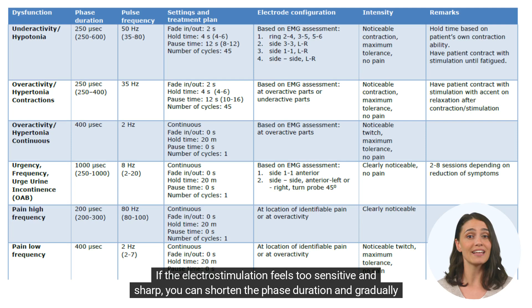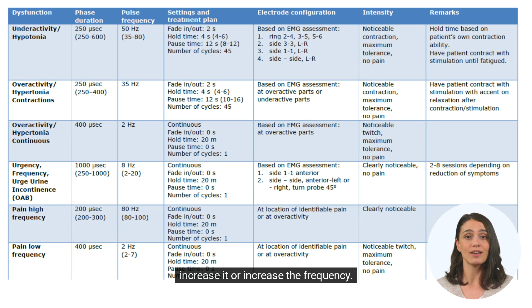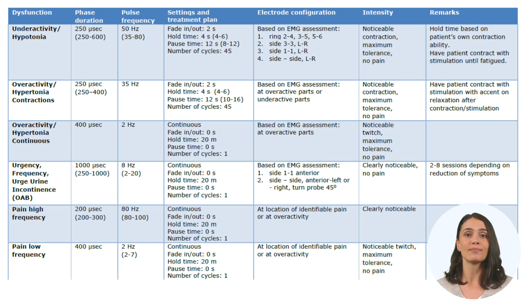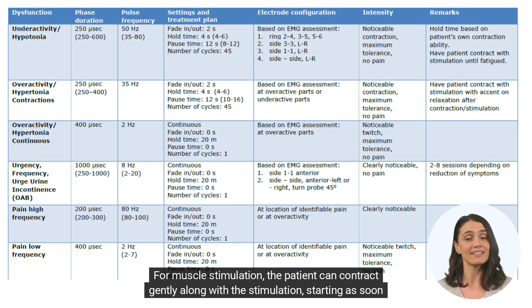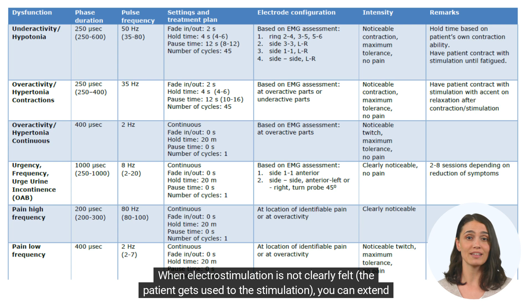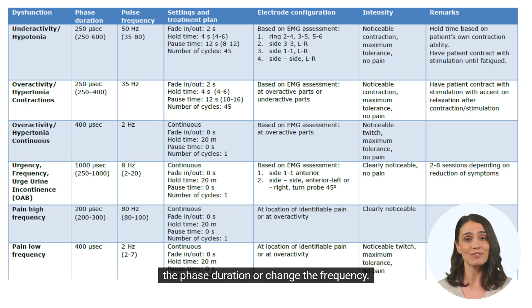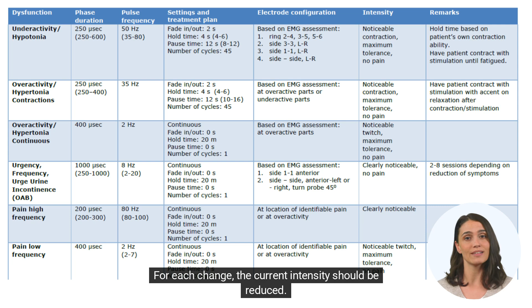If the electrostimulation feels too sensitive and sharp, you can shorten the phase duration and gradually increase it or increase the frequency. Additionally, you can slightly move the probe. For muscle stimulation, the patient can contract gently along with the stimulation, starting as soon as they feel something during the fade-in. When electrostimulation is not clearly felt, the patient gets used to the stimulation, you can extend the phase duration or change the frequency. For each change, the current intensity should be reduced.